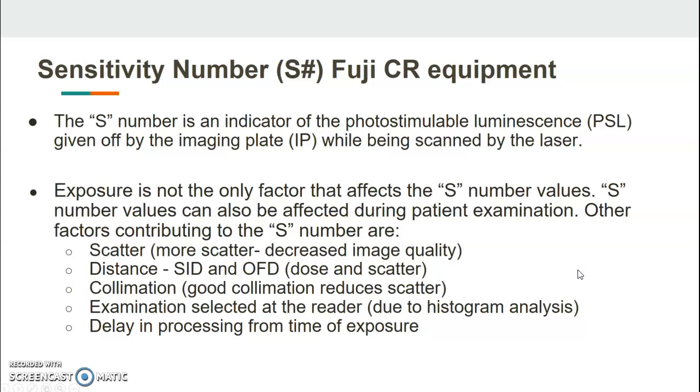Just a little reminder about sensitivity numbers, that it's not just about technique. There's a lot of other factors that might be considered for the S number that you're getting. Just remember, if you're not centered to that CR cassette, your S number is not going to be accurate. If you're not at the correct SID, your number is not going to be accurate. Collimation will come into play. If your collimation is wide open, you have a lot of scatter hitting your plate, it's going to read that as well. So it's not just technique, but technique is sort of the primary.